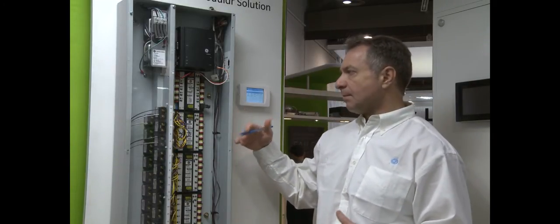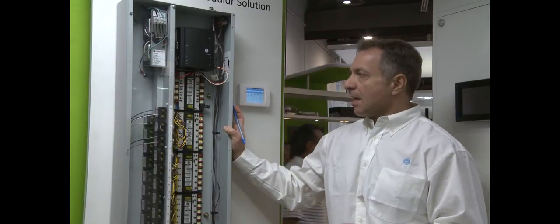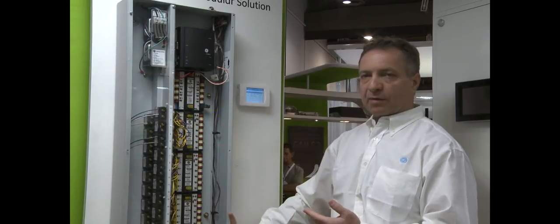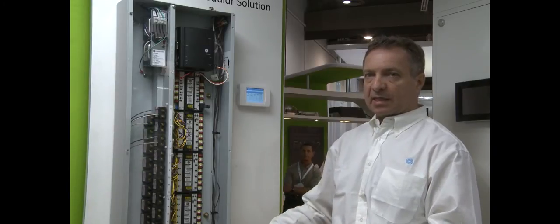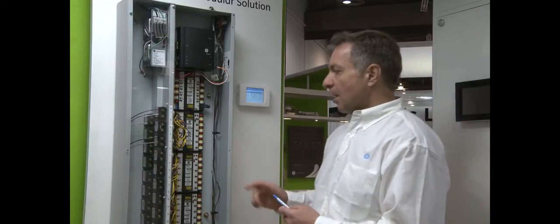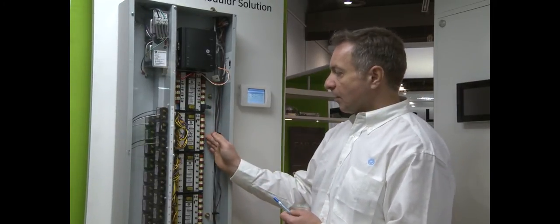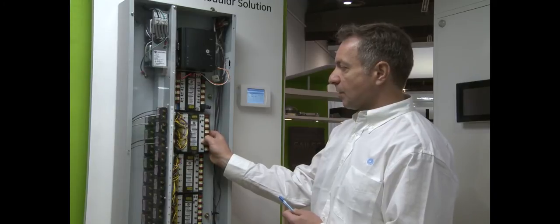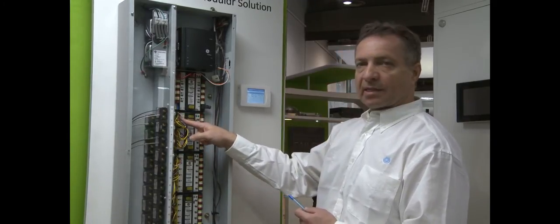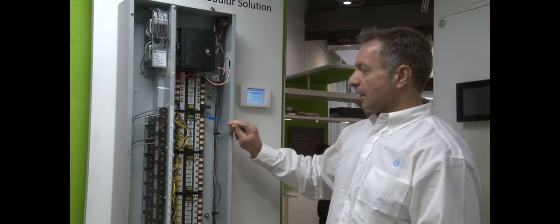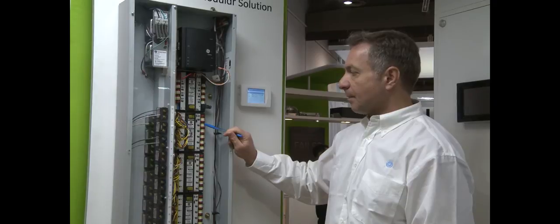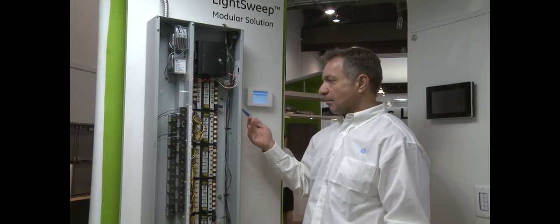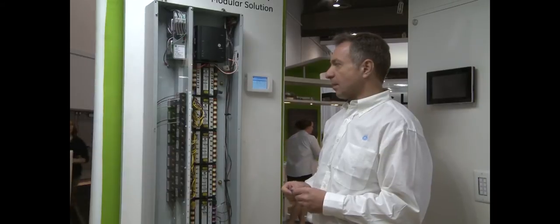The system is very flexible for different type of applications. Like I said, it can be built application specific. We don't need to add extra hardware if not needed. We can provide space if required and then they can plug in modules. One thing I wanted to highlight, all the modules are plug-in type. So actually they just snap into a couple of wings on the board. Connectors, the connection between the modules are using plug-in type connectors. Relays are also plug-in. And all the input wires are using spring terminals as well. So it's easy to add or to replace any of the controllers. If any of the functionality has to be changed, it's so easy to change that controller out in the field.